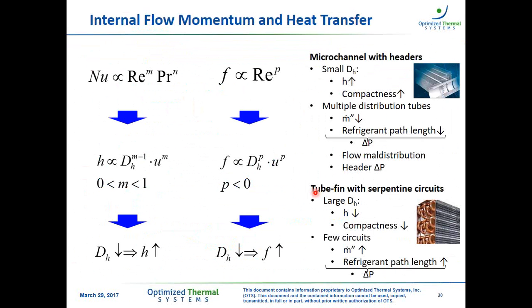Now, because by reducing the flow channel we have an increase in friction factor, the way microchannel concepts address the pressure drop is by having multiple distribution tubes or headers, where we reduce the mass flux in each channel and also reduce the overall refrigerant path length, so we can reduce the pressure drop within the tubes. But there are some disadvantages of doing so. We can have flow maldistribution or even additional header pressure drop, and these things are advantages of tube fin with serpentine circuits, where they don't exist.